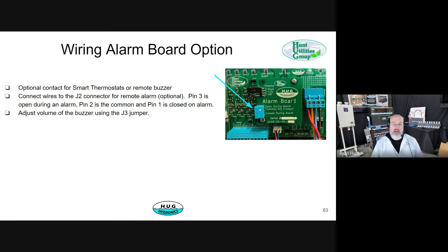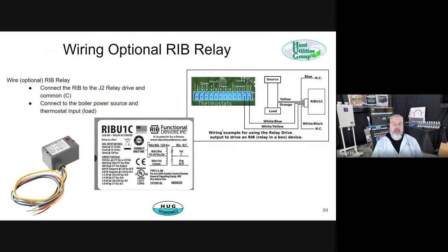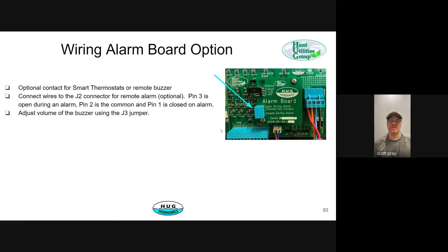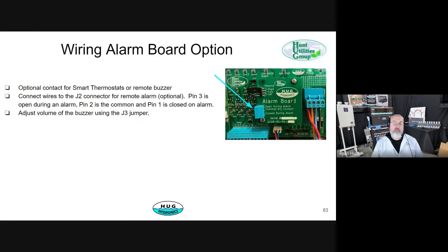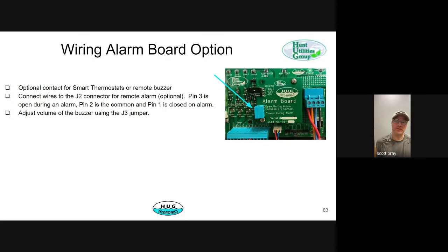So the alarm board option makes an electrical contact when the alarm happens. Some thermostats, smart thermostats, will have an alarm input that you can configure. The one we sell, we know how to configure that one so that it will send you a notice. I don't know if it's email or text. It'll send that to you when the alarm goes off. Is that a low temperature? Is that what that is? That's low water alarm. Oh, it's the low water. Yeah.